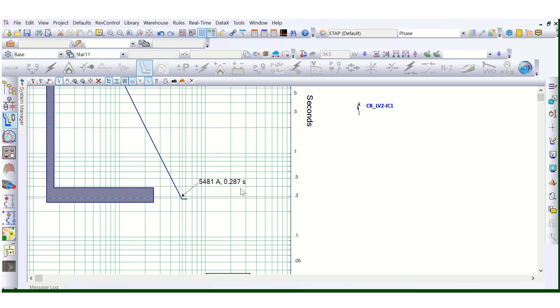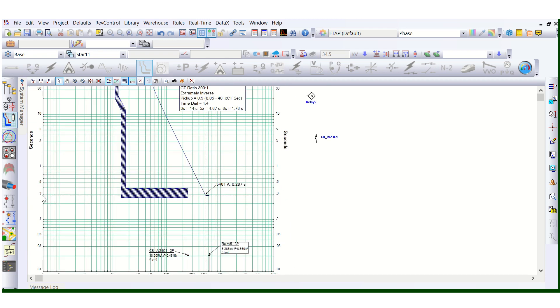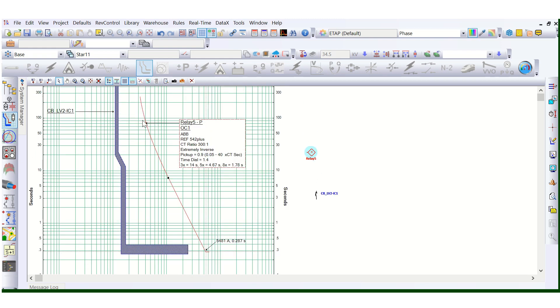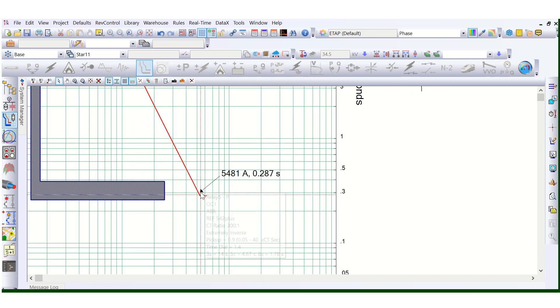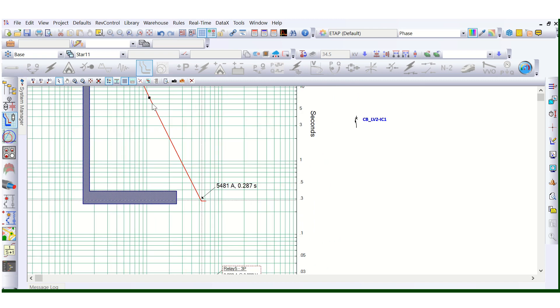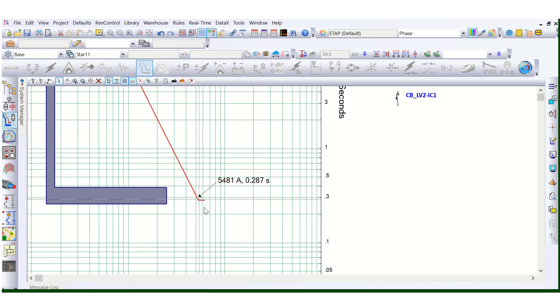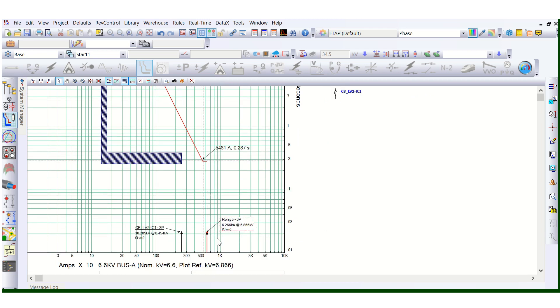This is almost 0.287 seconds from the curve — less than 0.3 seconds, approximately 0.287 seconds. Up to this point, this IDMT 51 will continue its inverse characteristic, and after that this will be definite time — just like a straight line, as you can see when it is clipped.